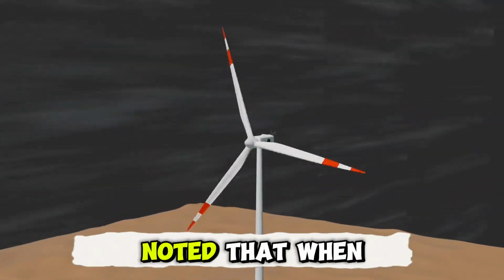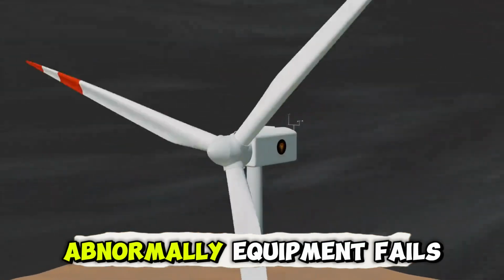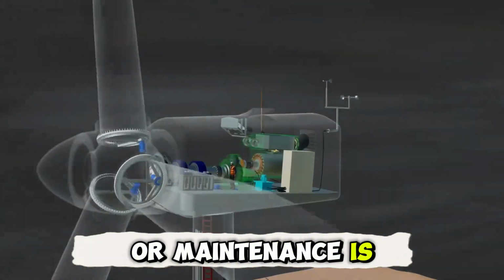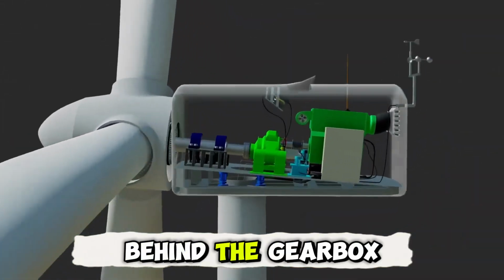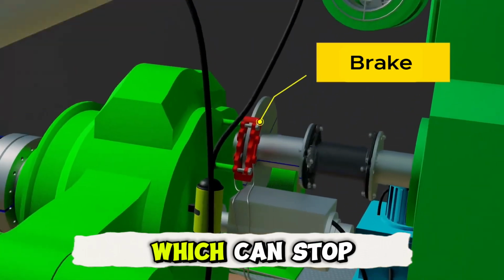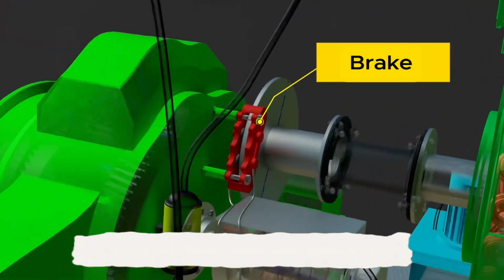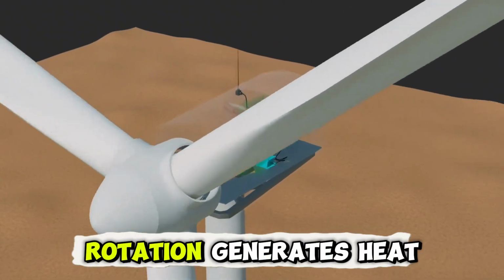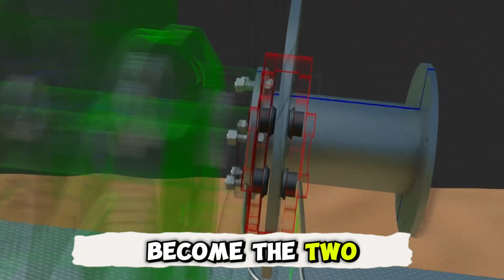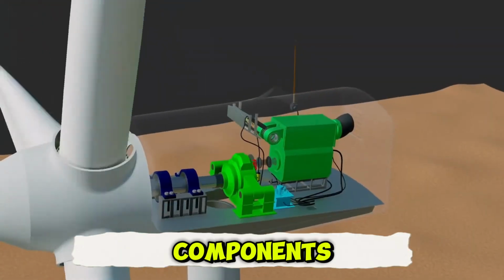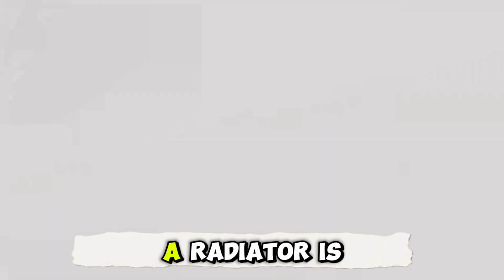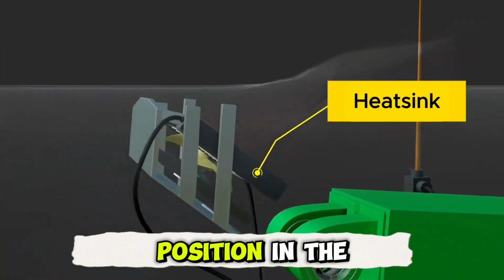It should be noted that when wind speed increases abnormally, equipment fails, or maintenance is required, at this position behind the gearbox, there is also a brake which can stop the windmill directly. Additionally, because mechanical rotation generates heat, the gearbox and the generator become the 2 main heat-generating components. In order to cool the gearbox, a radiator is installed at this position in the nacelle.